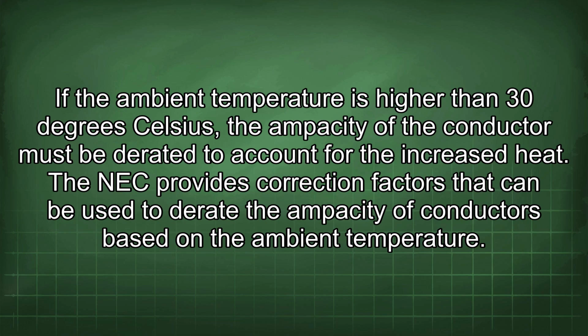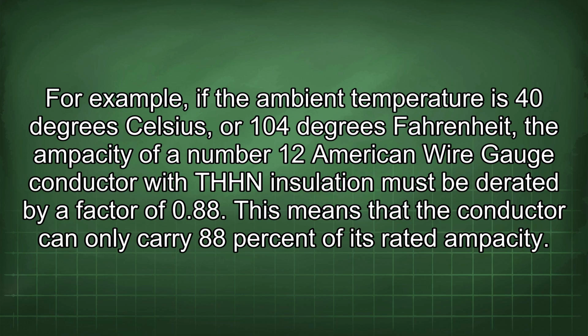The NEC provides correction factors that can be used to derate the ampacity of conductors based on the ambient temperature. For example, if the ambient temperature is 40 degrees Celsius or 104 degrees Fahrenheit, the ampacity of a number 12 American wire gauge conductor with THHN insulation must be derated by a factor of 0.88.